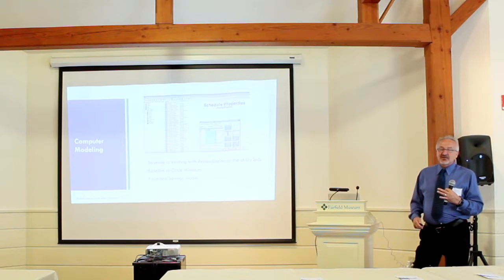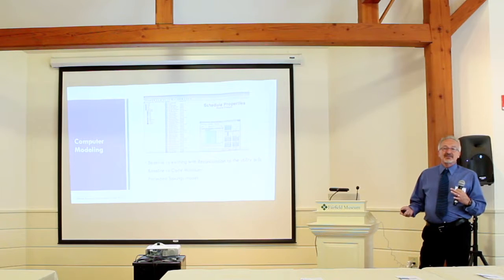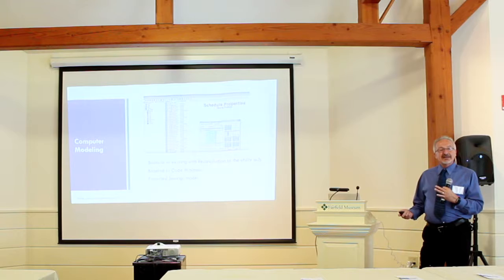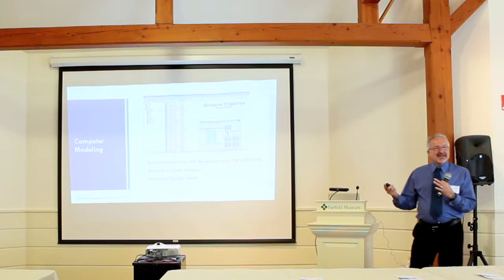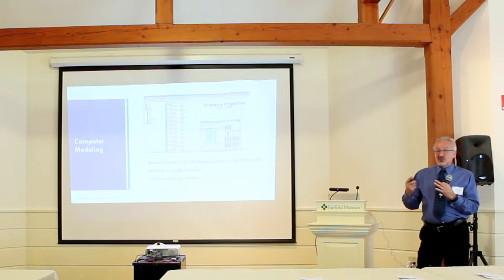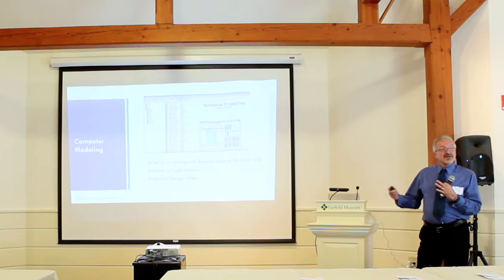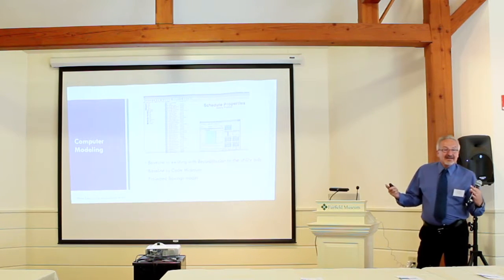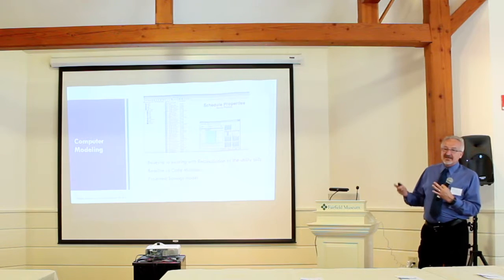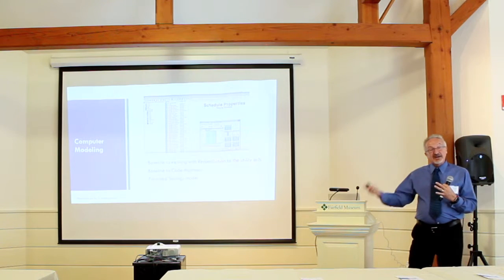What is this doing? I'm going to change out, well, how is it going to affect the lighting? My lighting, I'm going to put LED lighting in, but when you put LED lighting in, if you look at the modeling, well, a funny thing happens. Your heating goes up. You say, well, why did my heating go up? Because the watts from your lights put heat into the building, so the lighting actually increased your heating. So the modeling takes that into effect. But it also reduced my cooling load. So now I have less of a cooling load in the building. And so just by changing that one thing, changing the lighting affected the HVAC system, both your gas consumption and your energy from HVAC.